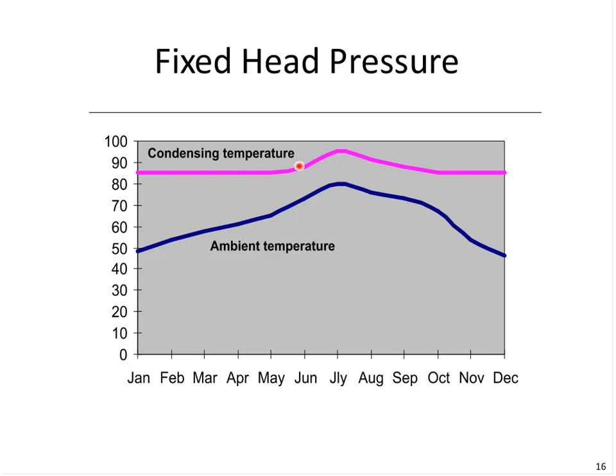Notice here we get a hot day in the middle of summer and ambient goes up. Of course, our condensing temperature will just rise with the heat of the day. But out here in the wintertime, when we could be condensing maybe down here about 10 degrees or so above the ambient, we're just not taking advantage of it.